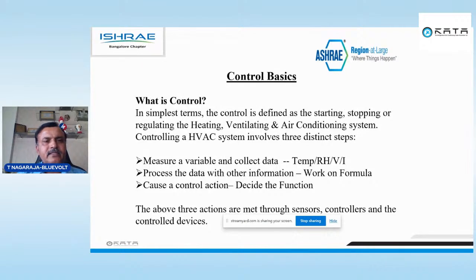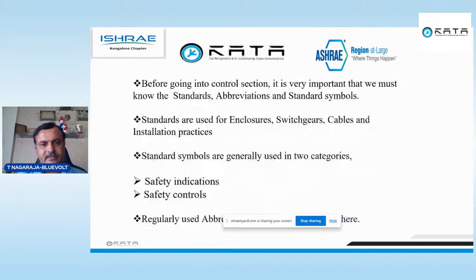Then what is the control? In simplest terms, control is defined as starting, stopping, or regulating our air conditioning systems. What is starting, stopping, or regulating? It means first measuring the required variables. That means collect the data, whether temperature, RH, voltage, current, whatever variable data we have to collect. Then process the data. That means we want only 24 degrees, or my compressor should run on this much load to deliver this much load. Then you cause the control. Control means you switch on, switch off, or regulate, that means vary the load. The above three actions are met only through sensors, controllers, and control devices.